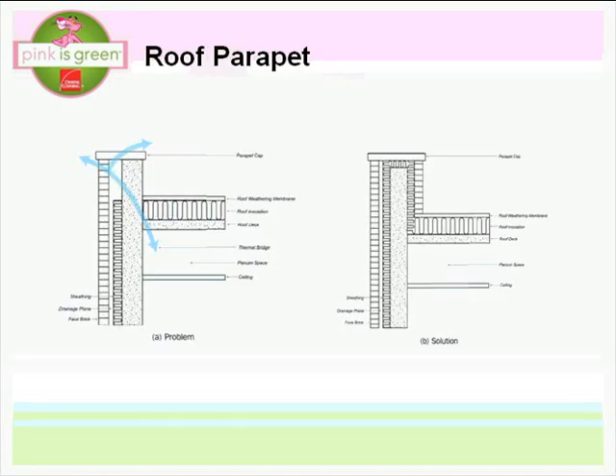In terms of roofs, increased wall insulation is a classic example, and then we have increased roof insulation, and then we have an effective thermal bridge because those two are not continuous. So for the 50% guide, the recommendation is that we have continuity of that exterior wall insulation up and over the parapet, and it connects down to the roof insulation so that there's no thermal bridge to short circuit the effectiveness of the insulation.